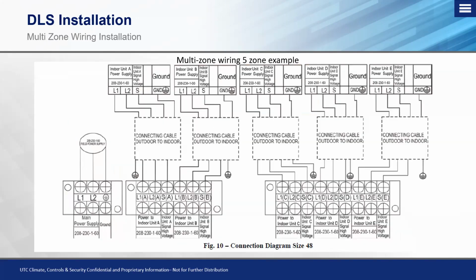Now you can see on here in the multi-zones, this is where things can get a little tricky, and why it's extremely important to label your power and communication lines when you have a 5-headed, a 4-headed, or a 3-headed system. Now you can see on here you have your L1 and L2 for zone A, zone B, zone C, D, and E. So it's very easy to get these lines crisscrossed.